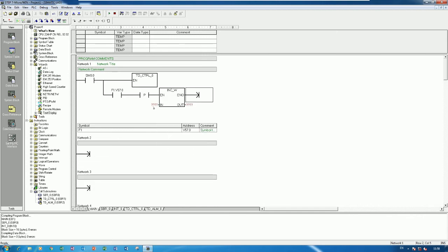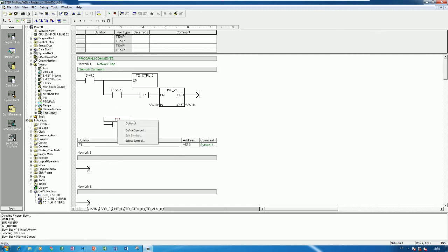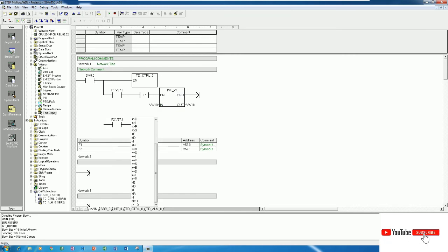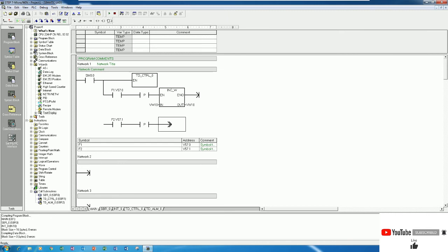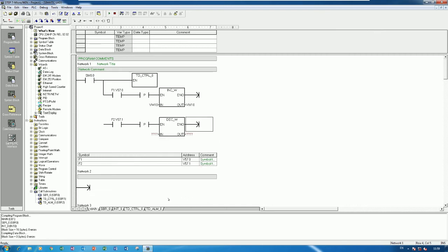After the positive edge contact, I will use the Increment Word function (INC_W). The address we set in the wizard is VW10, so VW10 here as well. For F2 to decrease, I use F2 with a positive edge contact and the Decrement Word function (DEC_W) on VW10.